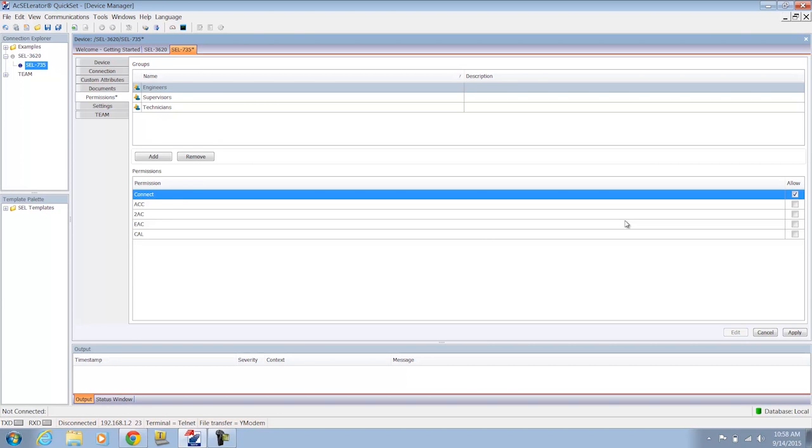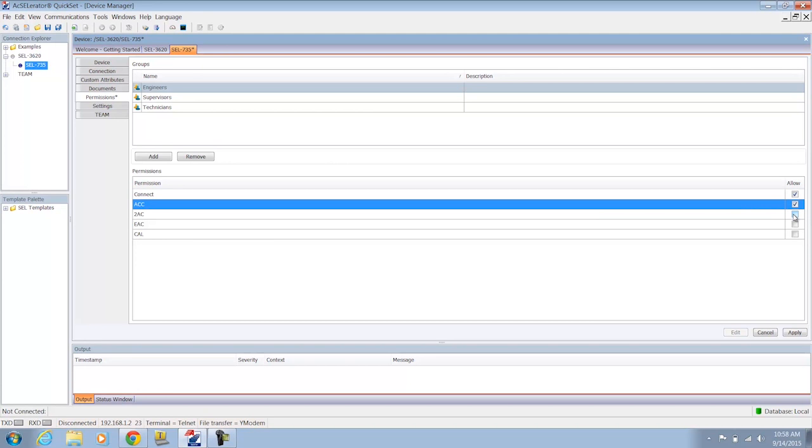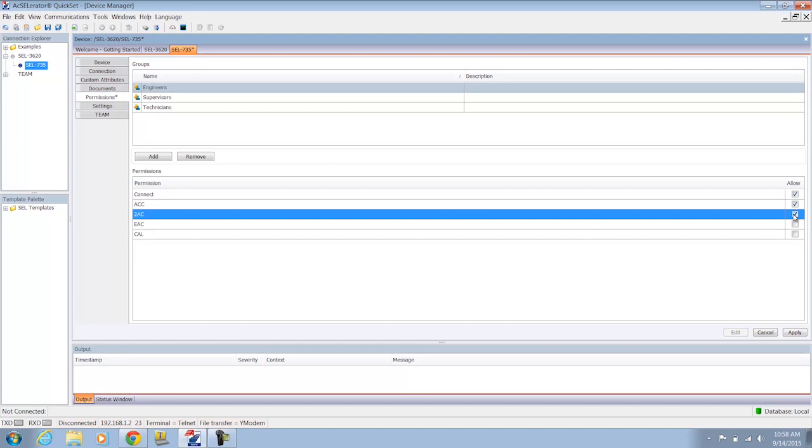2AC is where you can actually create changes on the relay, so you can clear your history record. Or you can go through and make a settings change. And there's various other access levels on most SEL relays as well. Please refer to your individual relay product manual for more information about what the various account levels do on those devices. But suffice it to say I'm going to add the connect level privilege, the ACC level privilege, and the 2AC level privilege for any member of the engineers group that wants to access this device.